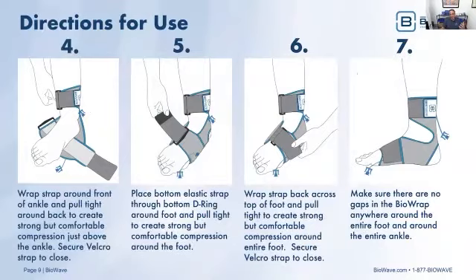Now we're going to repeat that process for the lower strap. You pull it through the D-ring and pull it tight. It's very important to make sure that there are no gaps occurring anywhere along the perimeter of that electrode. That goes for the upper electrode as well. Then you pull that compression strap back across the front of the foot and secure it tight with the Velcro strap. When you're all done, again, check to make sure there are no gaps anywhere. It tends to occur more on the edges of the foot and sometimes the edges just proximal to the ankle. We want to make sure there's good conduction between the silver fabric and the skin throughout the entire circumference of the foot, or the circumference just proximal to the ankle.